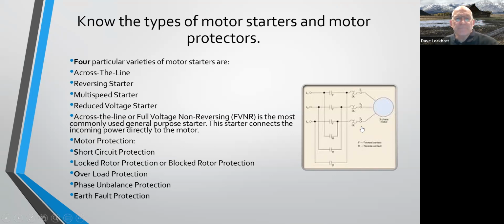Also, motor protection. For our motors, you got short circuit protection, you got locked rotor protection or blocked rotor protection, you got overload protection, phase unbalance protection, and earth fault protection, basically ground fault. One thing I noticed when I was looking at the internet, you can remember those by the word SLOPE. So I bolded those right there. So those are your typical protections to protect the motor.